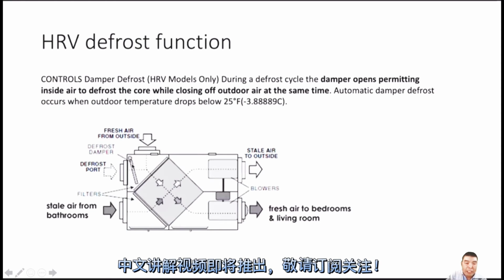So after that, for example, if we need a defrost, this damper will open and block here, blocking the intake from the outside. That means it sucks in the inside air, like the 22 degree air from here, and it goes through the heat exchanger. That makes the frost or ice on the heat exchanger melt. If you open the door and see a lot of frost or ice, that's not normal. It shouldn't have lots of ice there. So maybe it's a damper problem and it cannot defrost.